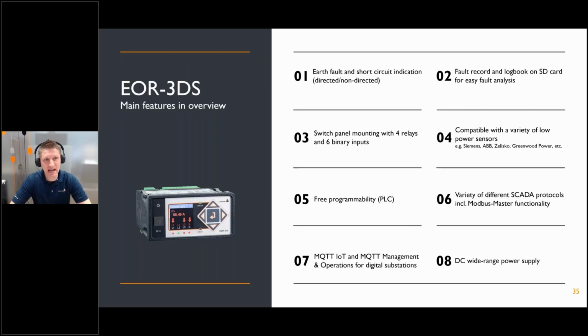So the main features again now of the EOR-3DS in the overview. We have sophisticated Earth fault and short circuit indication with additional algorithms. We also have fault records and logbooks here that can be saved also on an SD card, but can also be read out via software from remote. Of course, fault records can be up to 100 seconds if you really want to use that. Standard is 2 seconds. It's a switch panel mounting device with 4 relays and 6 binary inputs, especially for remote control of compact switchgear stations, and meant for that.